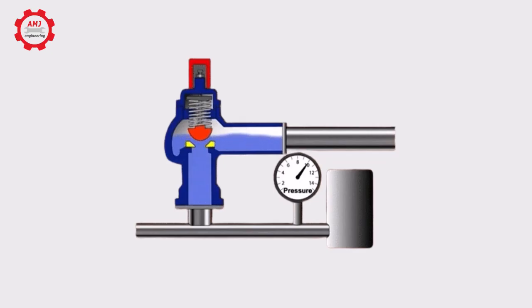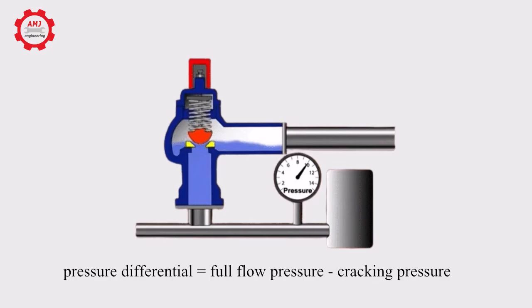When the valve is bypassing its full rated flow, it is in a state of full flow pressure. The difference between full flow and cracking pressure is sometimes known as pressure differential, also known as pressure override.